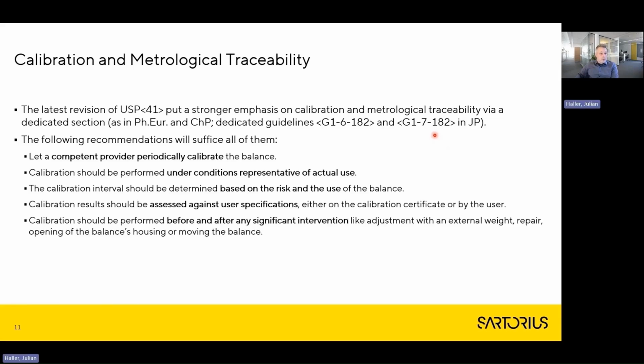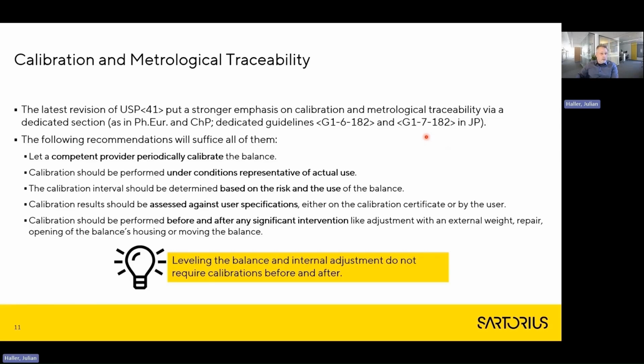Calibration should be performed before and after any significant intervention, like an adjustment with an external weight, repair, any opening of the balance's housing, or moving of the balance. Note that leveling the balance and adjustment with an internal weight do not require calibrations before and after, as they are not considered significant interventions.